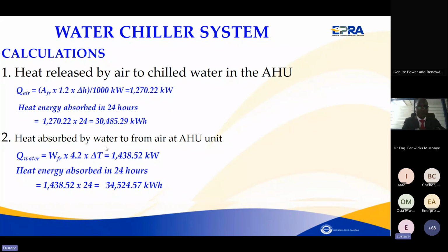You can see heat absorbed by air, absorbed by water from air at the AHU. You might be wondering, probably these things should be equal. No. The reason for calculating both is to establish the effectiveness or the efficiency of heat transfer of the AH unit. In ideal cases, they should be equal. But in the real sense, there is some heat which has been absorbed by the parts, the coils, which has been used to increase the temperature of the coil or of the fins of the AHU unit.